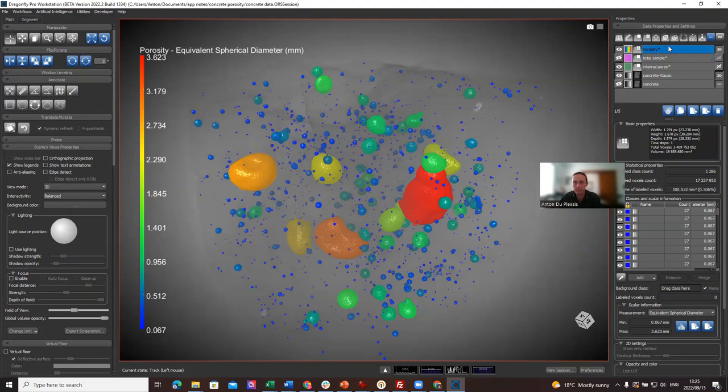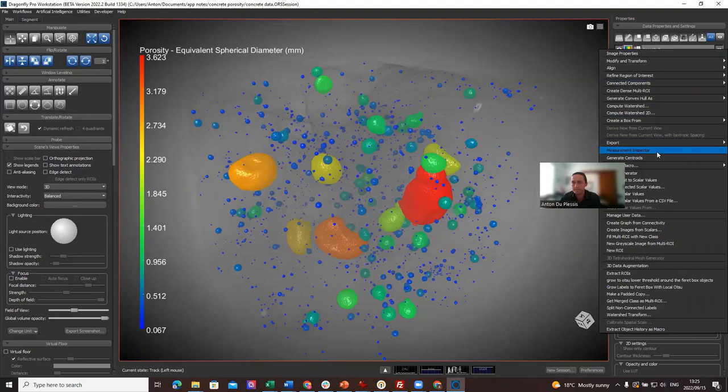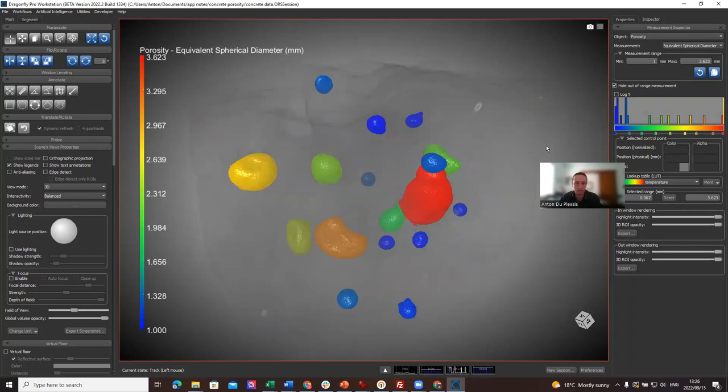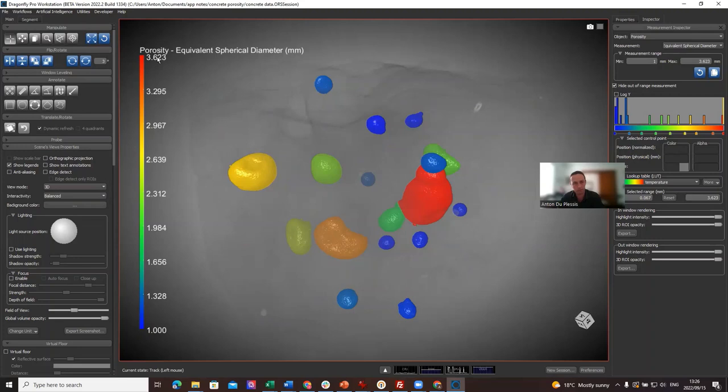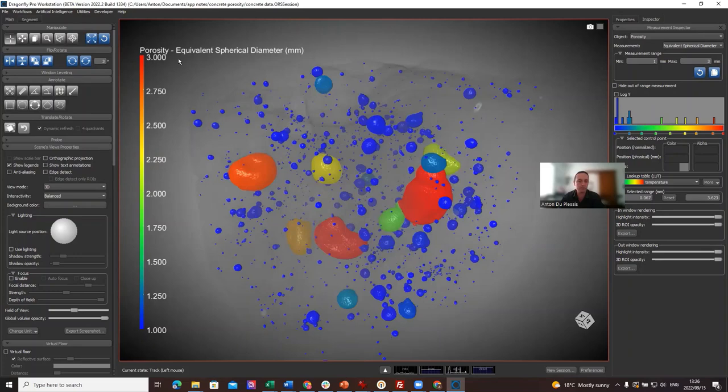So what I want to demonstrate briefly is if we want to visualize only the biggest pores but not change the data, we can right click and go to Measurement Inspector. And we can say, okay, show me all the pores bigger than one millimeter only. These are all the pores bigger than one millimeter. They are hidden out of range, or you can show all those below. So the one millimeter pores are now blue and the biggest ones are red. So this is where you change the legend range. You can make it from one to three millimeters, and you don't have to hide out of range. Now everything above three millimeters is red and below one millimeter is blue. Let's close Measurement Inspector.